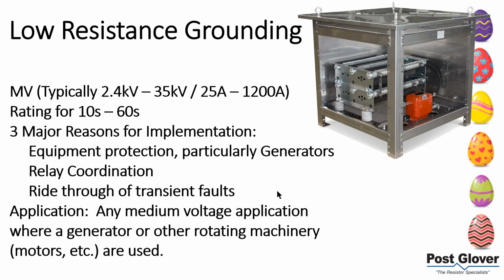We'll go into that a little bit. Relay coordination. If you lower the amount of current that flows, then you're able to coordinate better. You have more time because your system can operate longer at a lower current, and so therefore you have more time to coordinate properly versus trying to basically instantaneously trip and potentially tripping your entire system offline or a larger portion than you desire.